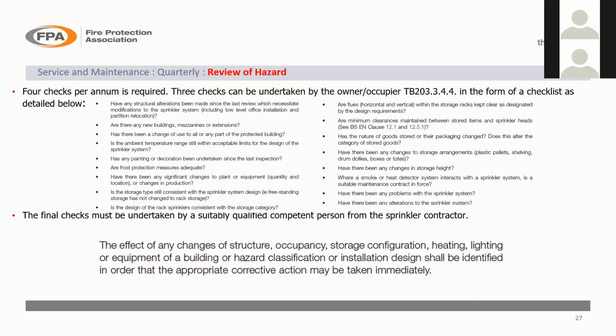The reason for this is during the operation of a building, obviously things like the usage can change. You could add new buildings. There could be things like, have you had it painted or decorated? Have you changed your occupancy? Are you making a product now that you weren't making before? So the layout's changed. What you're storing on site has changed, the way that you're storing it. All these factors have a big bearing on what the sprinkler system was originally designed to do.